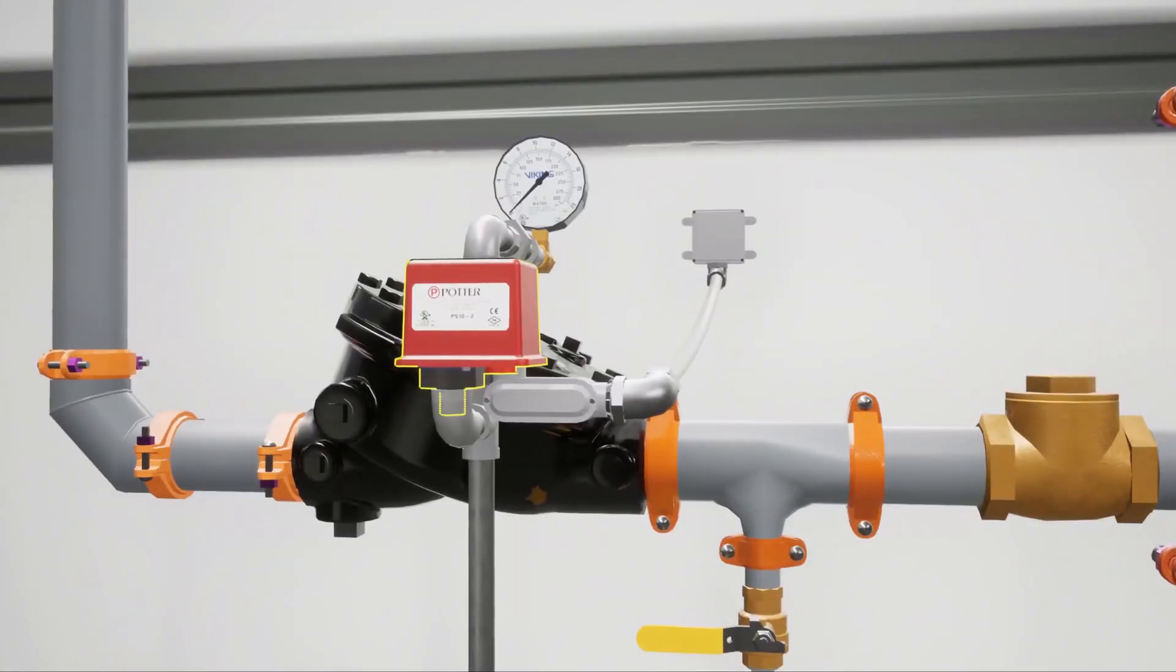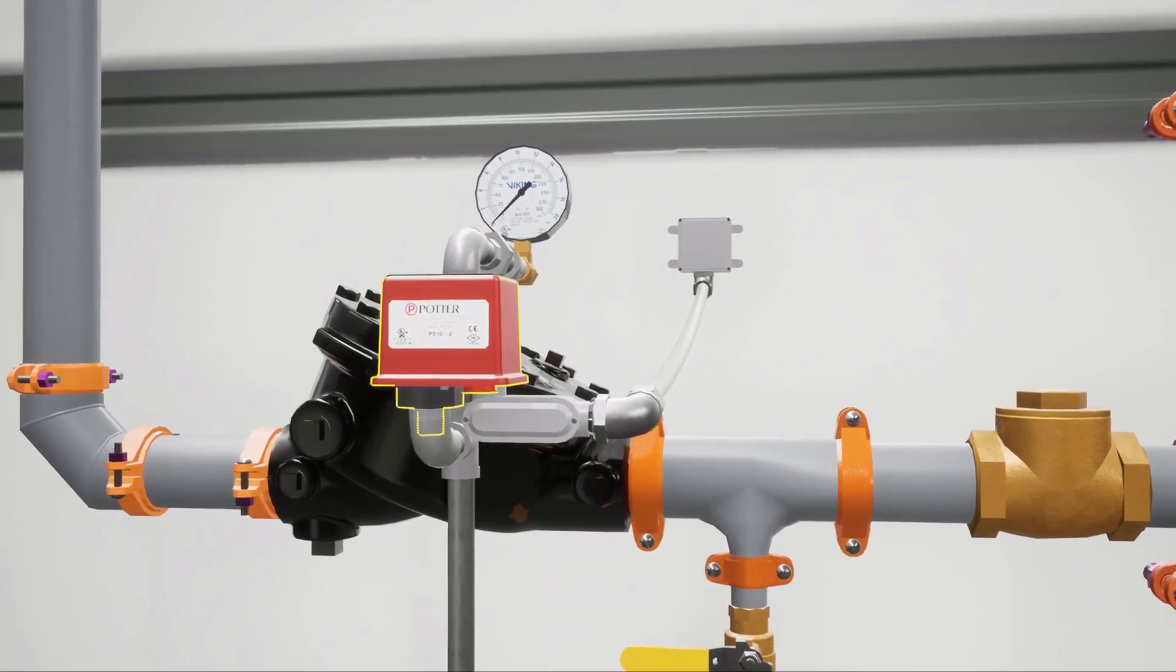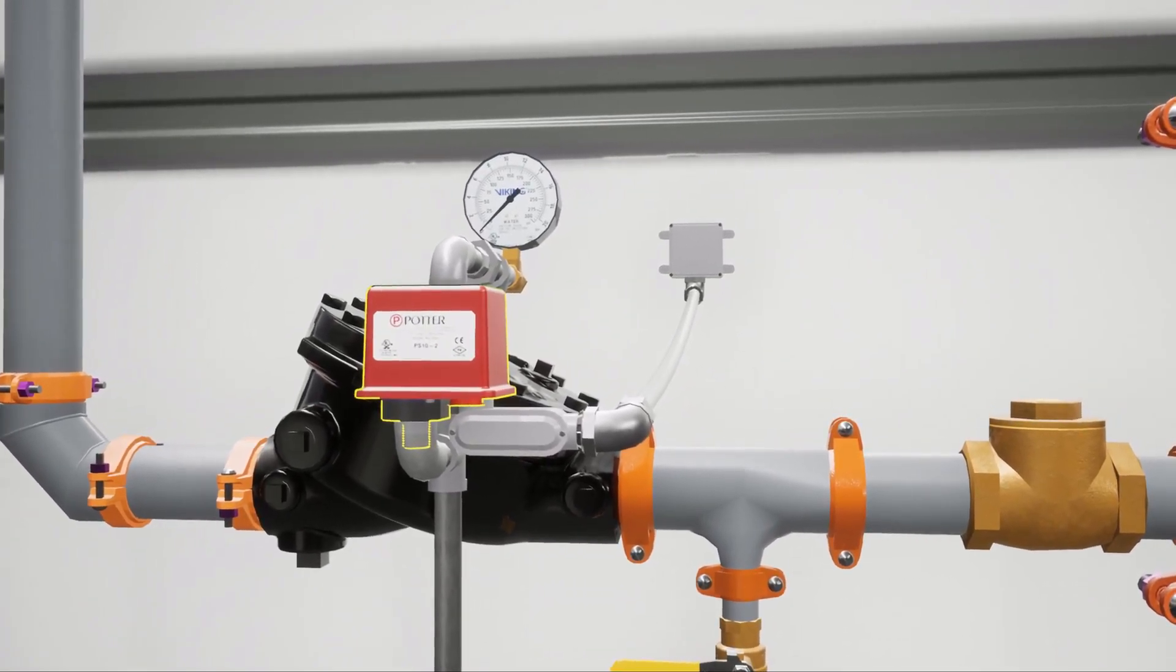The drop of prime pressure causes the priming line pressure switch to activate. Priming line pressure switches are required for Factory Mutual global approval.